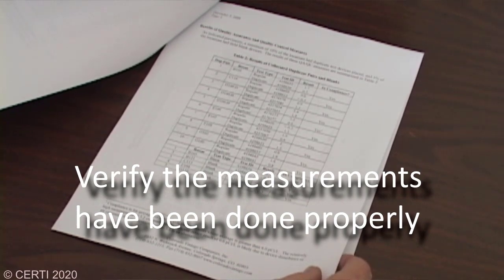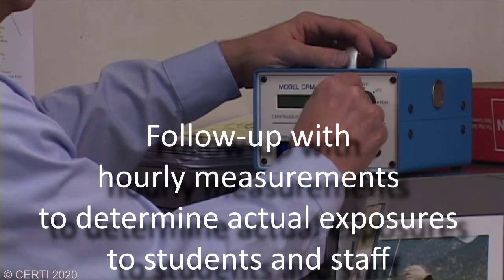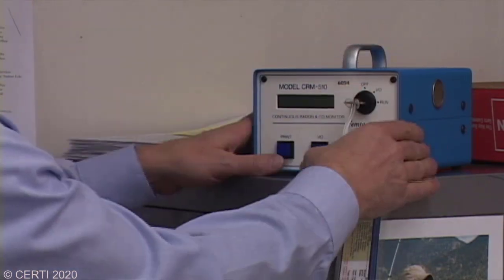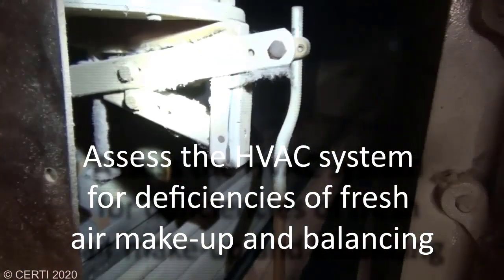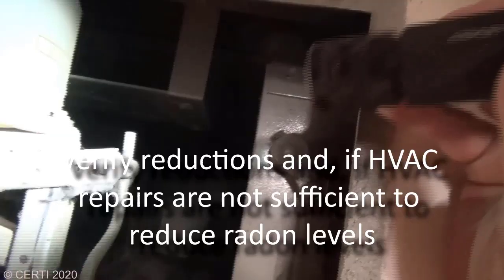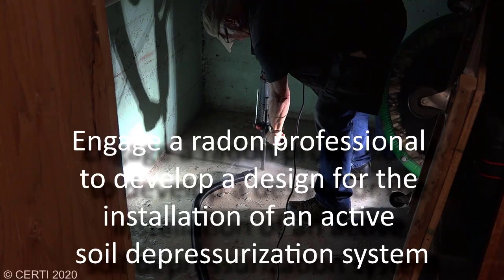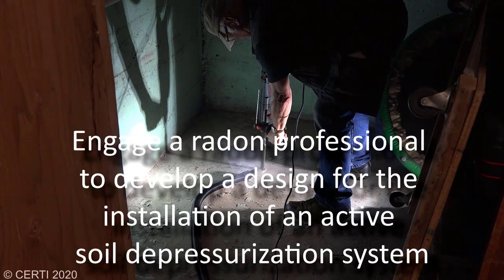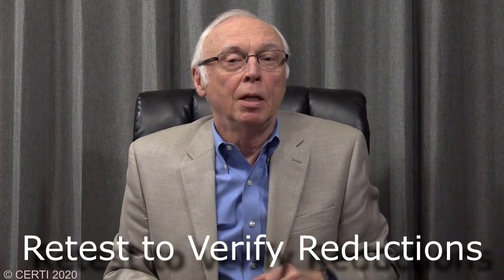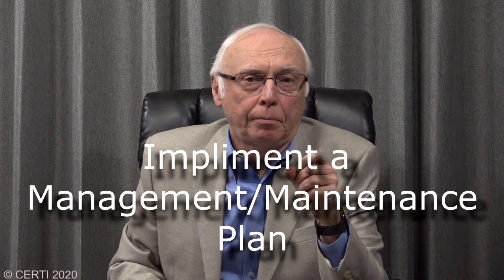So as you can see, when addressing a radon concern in a school, there are several steps that can be taken in a logical sequence. First, verify the measurements have been done properly. Follow up with hourly measurements to determine actual exposures to students and staff. Assess the HVAC system for deficiencies of fresh air makeup and balancing. Verify reductions, and if HVAC systems are not sufficient to reduce radon levels, engage a radon professional to develop a design for the installation of an active soil depressurization system. Then implement the design. But always retest the school to verify reductions. And then implement a management maintenance plan.